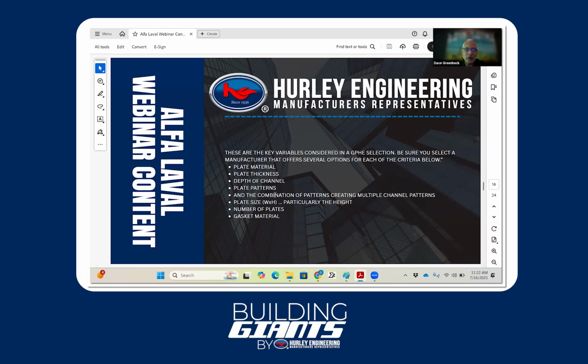This is very important, because you could go into laminar flow or less turbulent flow that could encourage scale if you're doing variable flow conditions. Or if you're doing variable or different flows on either side of the plate, the hot side's X flow and the cold side's 2X. If you don't have variability in the patterns on either side, you'd have to select for one, and the other could end up laminar or too low velocity, encouraging fouling prematurely.